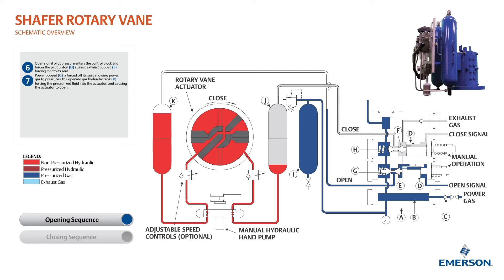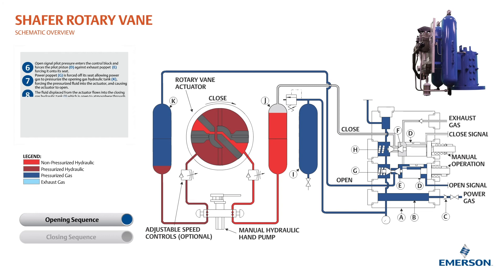This allows power gas to pressurize the opening gas hydraulic tank, forcing the pressurized fluid into the actuator and causing the actuator to open. The fluid displaced from the actuator flows into the closing gas hydraulic tank, which is open to atmosphere through the exhaust check valve in the poppet block.